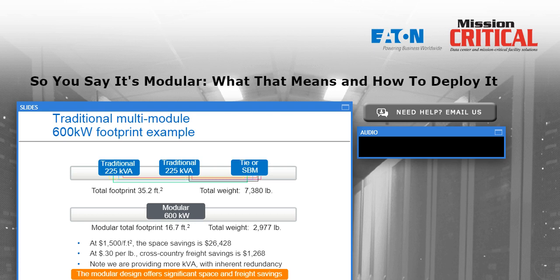Each 225 kVA has its own independent controls, and they're physically separate from each other. Each one generally will have its own discrete battery system, which might consist of 2 to 4 large battery cabinets that need to be deployed on each of those 2 UPSs. There's also the consideration for installation time and cost on site. The cabling from each UPS output and input to the tie cabinet, as well as battery connections and bypass connections, a fair amount of conduit and copper has to be deployed. The total footprint and total weight you see there, in this case, footprint around a little over 35 square feet.